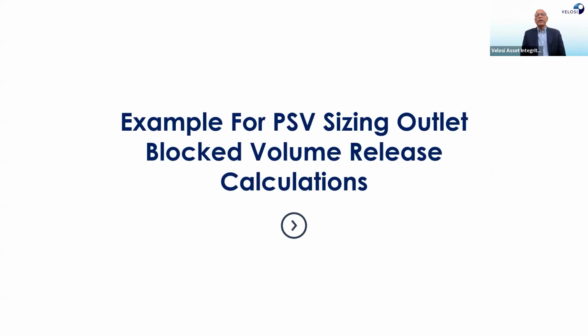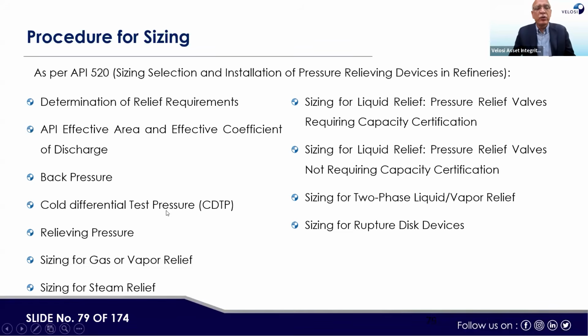Now, let me go through one example of PSV sizing for outlet blocked volume release calculation, just to make you familiar with how the PSV sizing is done. When we are using API 520, we determine the relief requirement, API effective area and effective coefficient of discharge, back pressure coming from the relief system, cold differential test pressure, relieving pressure, sizing for gas or vapor relief, sizing for steam relief. Well, there are various scenarios. Sizing for liquid relief, sizing of pressure relief valves not requiring capacity certification, sizing for two-phase liquid flow, sizing for the rupture disk. So if you see, before sizing what is important is relieving pressure, cold differential test pressure, back pressure, API effective area and effective coefficient of discharge, then there are various scenarios which are applicable.